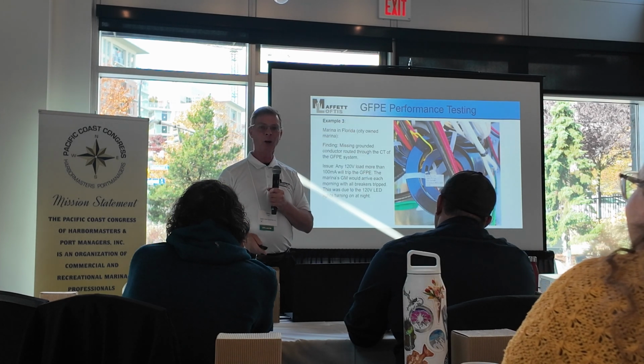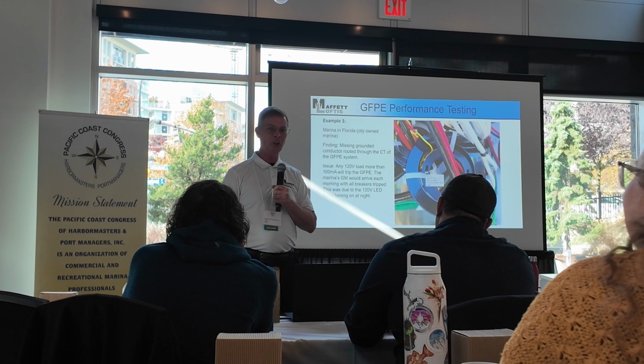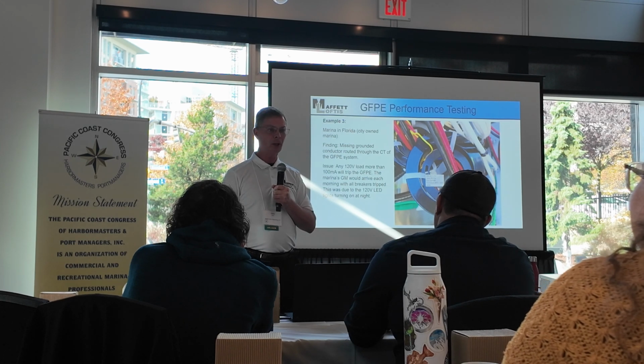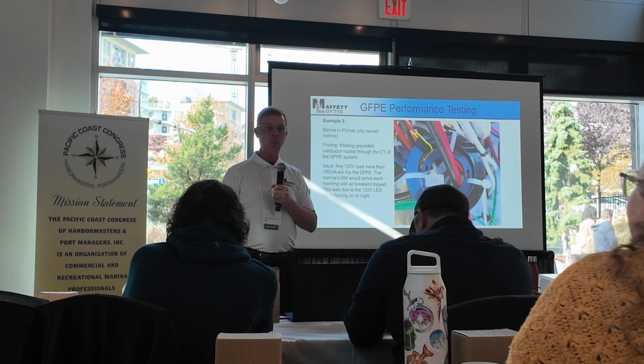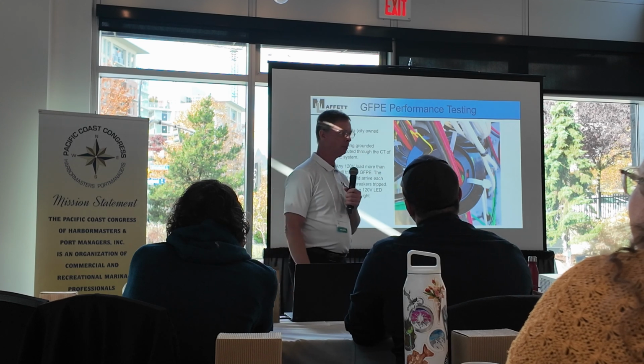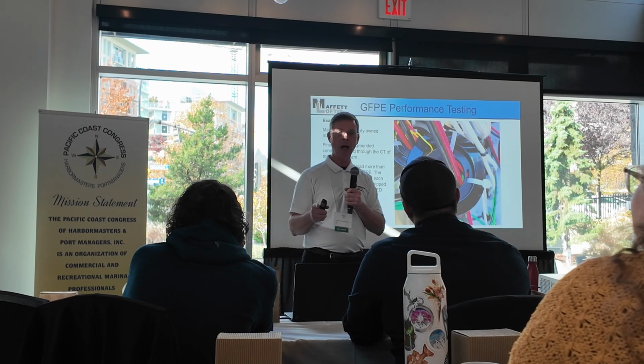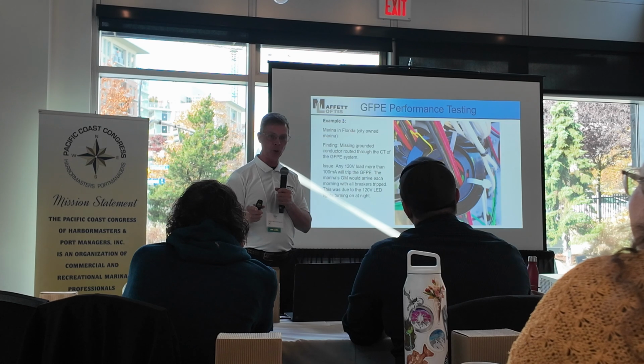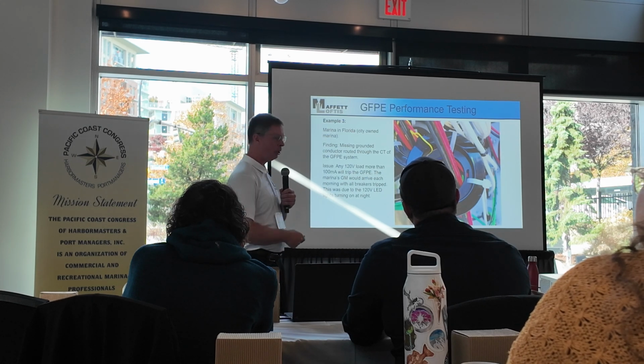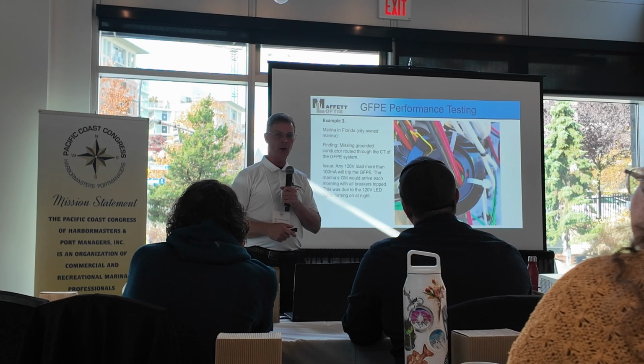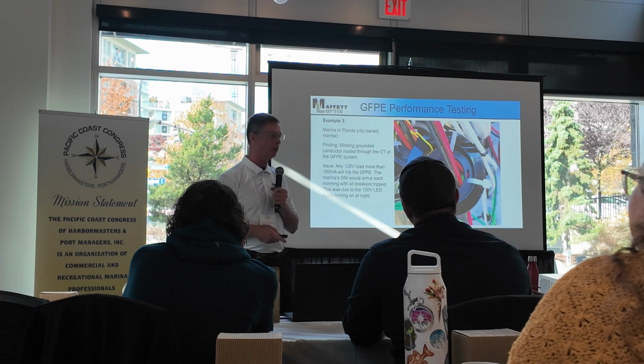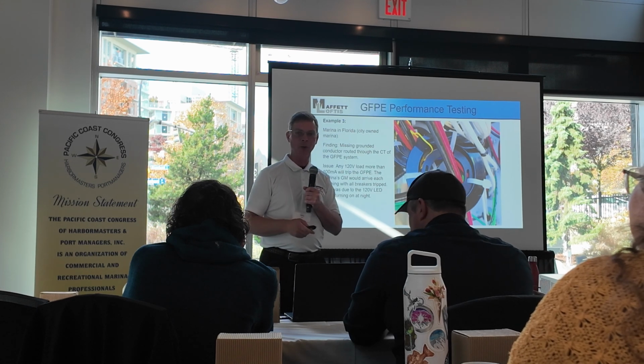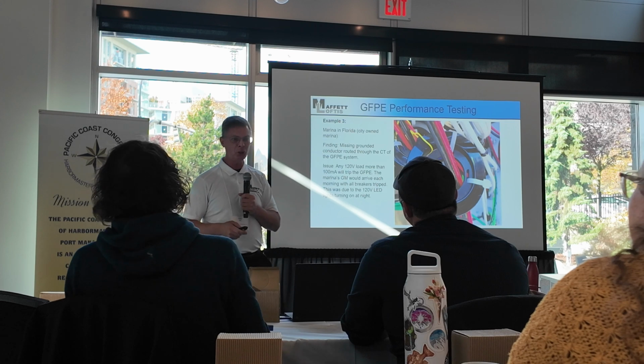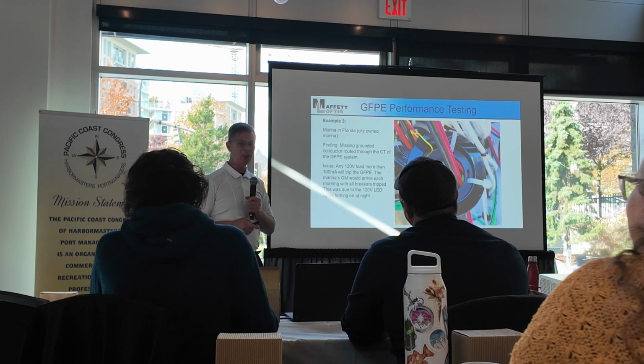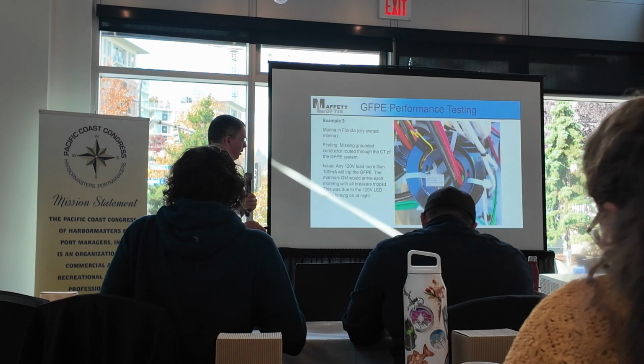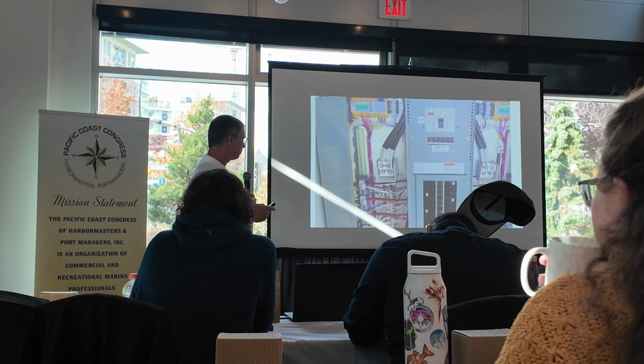I knew instantly what was going on. I told him, you don't have the neutral through the CT, do you? He says, I don't know, I thought I did. And what was happening, what comes on at night? Lights. 120 volt lights, which put neutral currents on the neutral wire, which created an imbalance, and this thing thought it was a leakage current. So every time the lights came on, it tripped the GFPE. The contractor would reset them in the morning and try to finish his work, and the next morning reset them again. It didn't even dawn on him to think about the lights when they were actually tripping it.